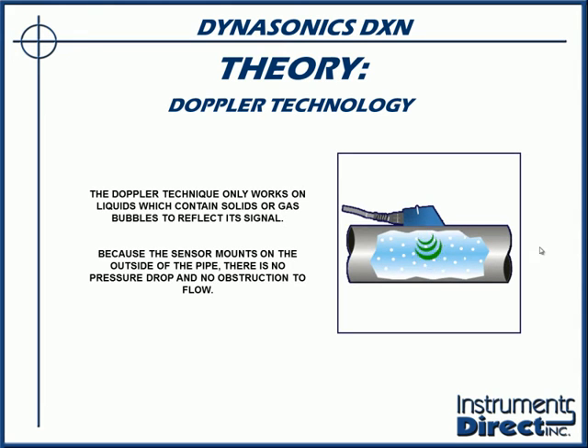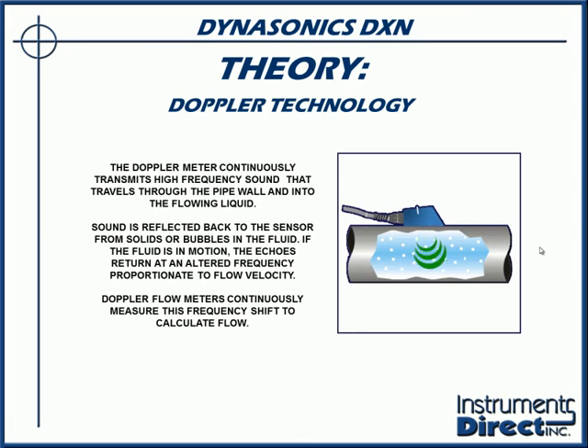So Dopplers are designed traditionally for slurry-like applications, sludge-like applications, or applications that don't have a lot of straight run of pipe, where you can reflect off of turbulence. Dopplers are not designed to work in applications that have no suspended solids. For example, a cup of tea. If you've got a cup of filtered tea, the liquid looks very opaque. You say, my goodness, look how dirty this liquid is. But they're all in solution. There are no suspended solids. Just like a glass of Sprite, it's clear and translucent, but there are a lot of suspended bubbles in there. The Doppler flow meter needs to have something to reflect its transmitted frequency back in order for it to work.